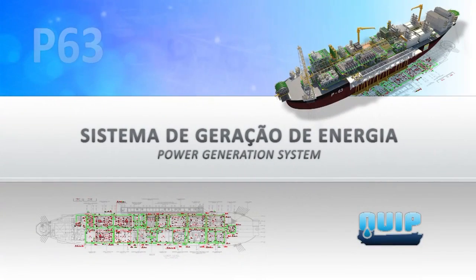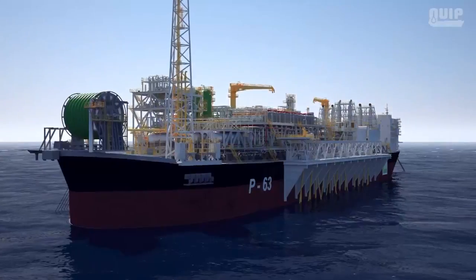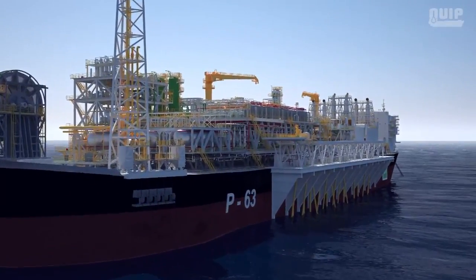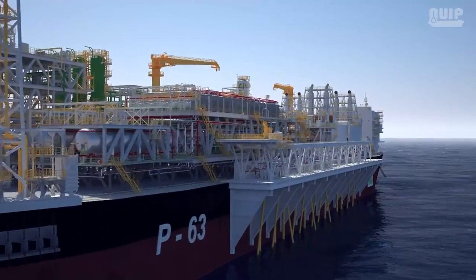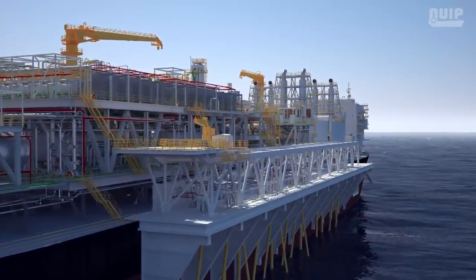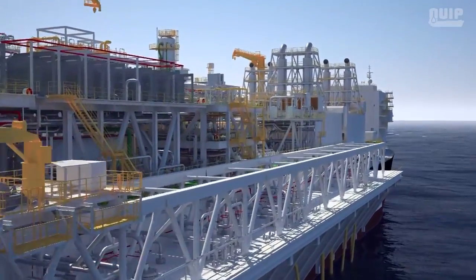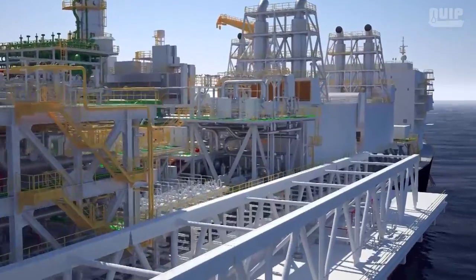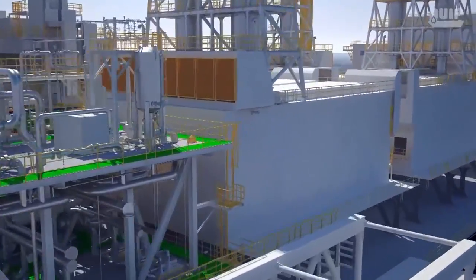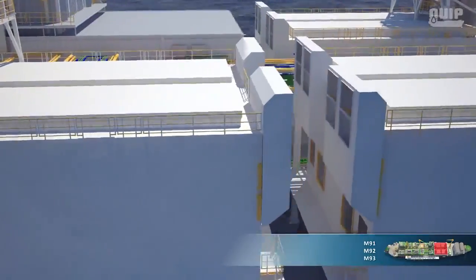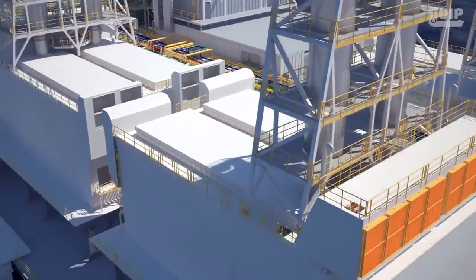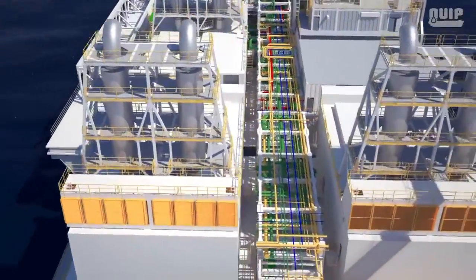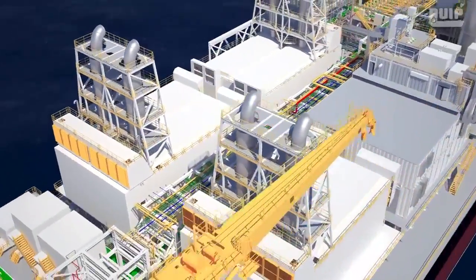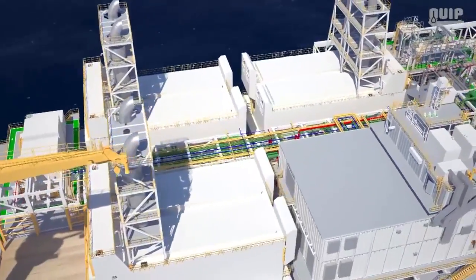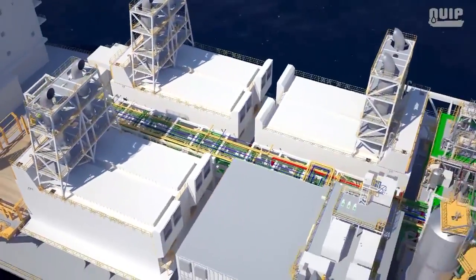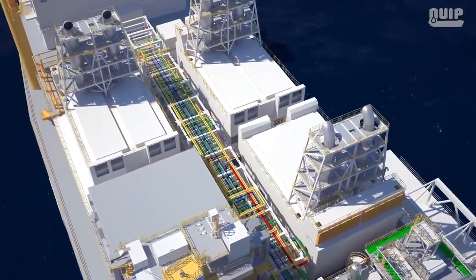Power generation system. The P63 power generation system was designed to attend the electricity consumption requirements of platforms P63 and P61. It is composed of 3 modules with a total capacity of 103 megawatts, driven by 6 motor generators. P63 will be the first platform with technology that allows for use of 3 types of fuel: fuel gas, processed crude oil, and diesel oil, according to availability over the production platform's years of operation.